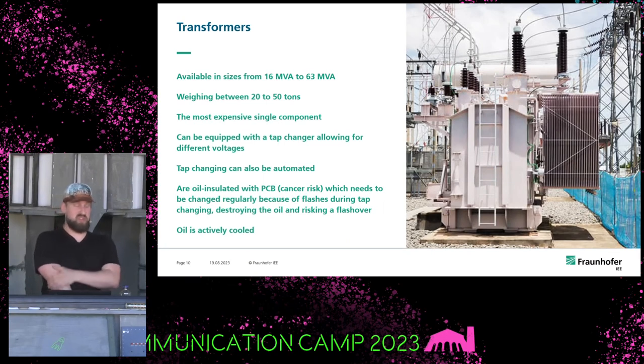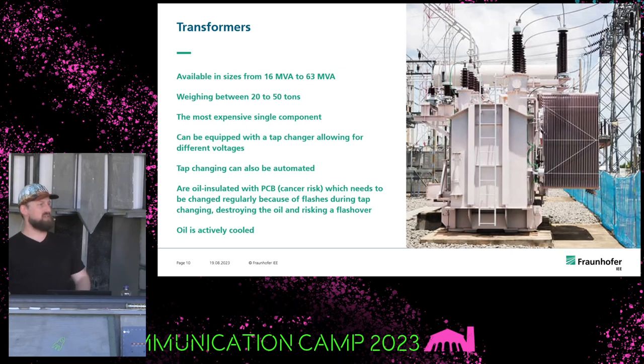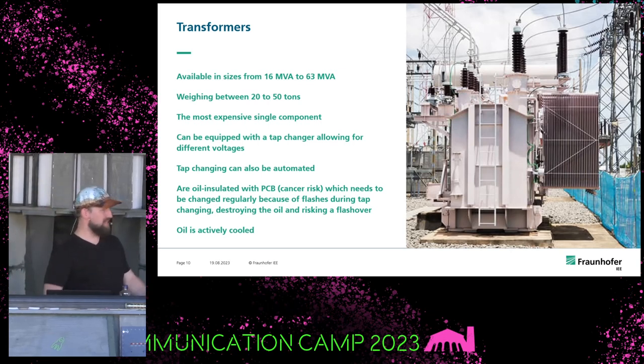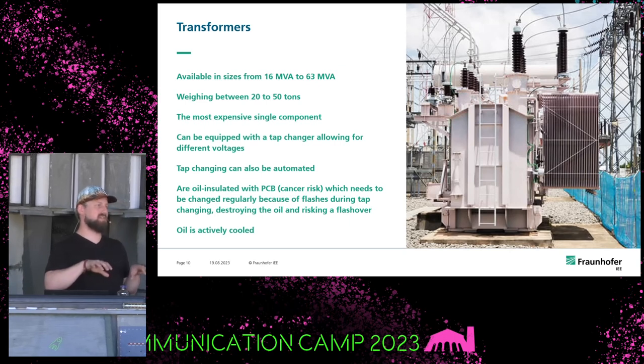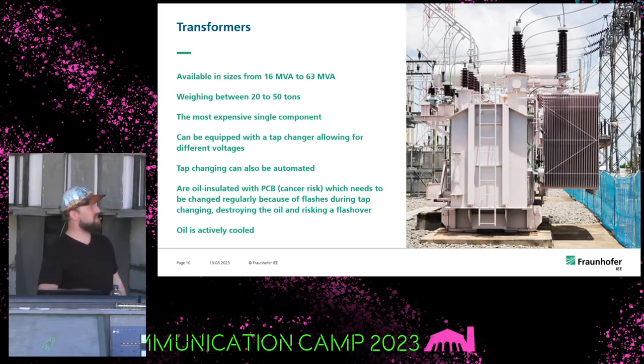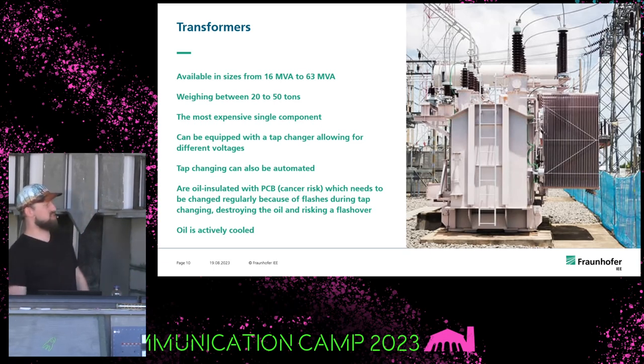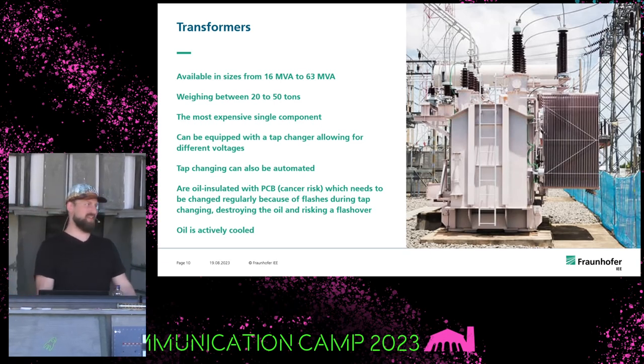There's one big problem: these things are really expensive and take a lot of time to build. As you can see here, they weigh about 20 to 50 tons, so you need a crane to supply them. If you visit a substation, you will see they always have one spare unit standing around in case of exchange. Normally you have two transformers because of N minus one safety, and these two transformers are normally calculated so that if one fails, the other can take over the whole load. Because normally building such a transformer takes years, so if you need one now, you will normally have to wait a year or even longer.